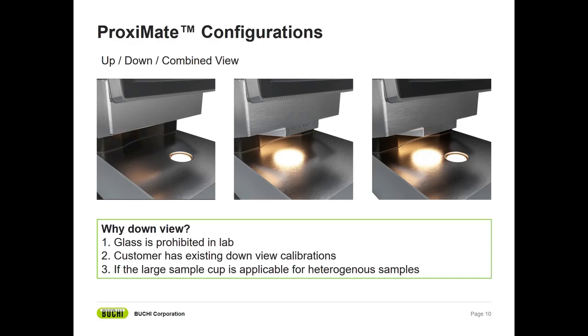I would estimate most labs are using UpView, but DownView does have its advantages. For example, if glass is prohibited and you need to use a plastic petri dish, then DownView will help so that we don't have to analyze through the plastic, since plastics can be inconsistent in allowing light to pass through. Also, if you're working on an older system with the DownView calibration, this will allow for easier transfer of that calibration to the newer one.